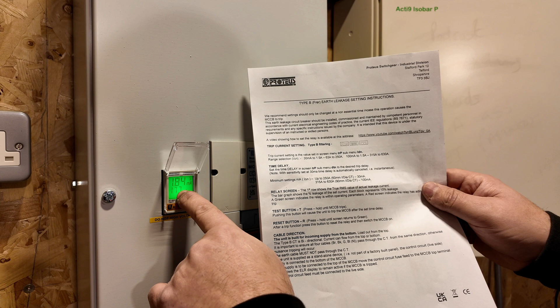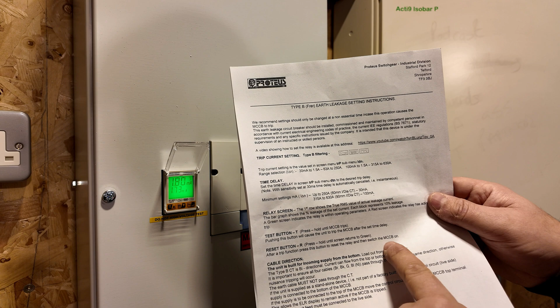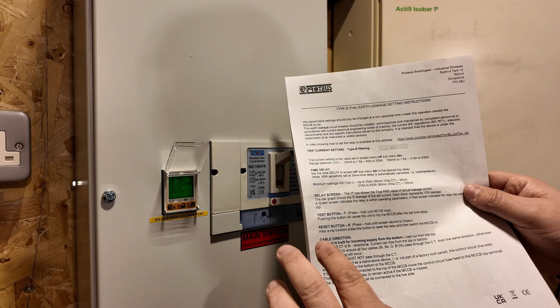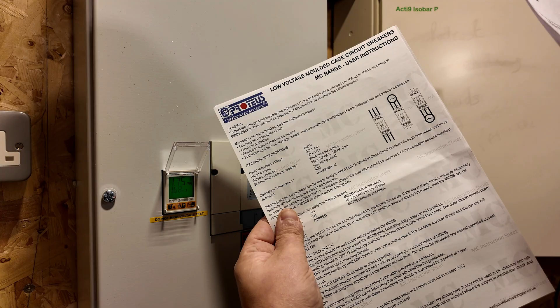You can press the test button and that'll trip the MCCB. So pushing this button will cause the unit to trip the MCCB after the set delay time. And then the reset button, you have to press that first so you can then reset the main RCD, and we'll show that happening in a minute. There's some other little bits of instructions in here that you get as well with a circuit chart and diagram. You've got your layout and rating there for the low voltage moulded case circuit breaker, and then you've got the little instruction sheet here which shows you how the relay works.